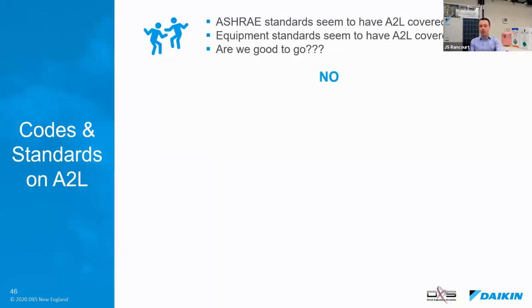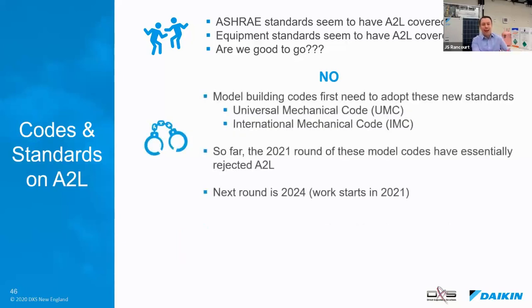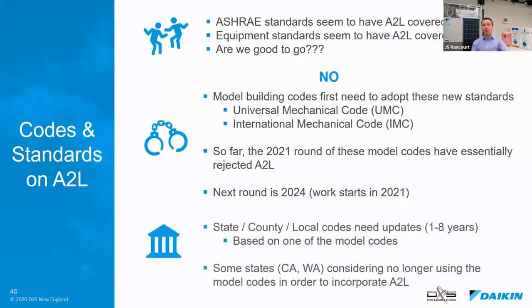These are standards, not building codes. Our handcuffs are at the model building code levels, the UMC and the IMC. These model building codes are the first ones to go, and then the states follow the model national codes. So far, the 2021 round of these model code updates, they have rejected the A2Ls. The next round is 2024. The work on that starts in 2021. So that's the next chance to get A2L and the new ASHRAE and the new UL into the model codes, UMC and IMC, at which point the different states are going to have to update their codes based on the model codes. And that can take anywhere from 1 to 8 years, depending on their cycles. So we're a long ways away from getting the new ASHRAE or the new UL into our building codes.